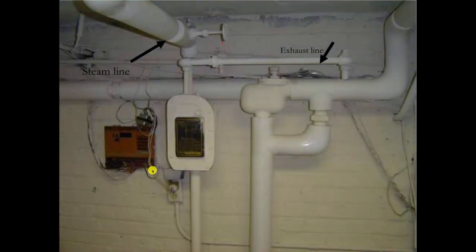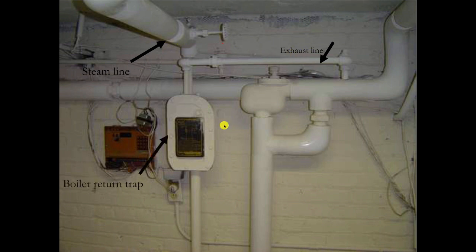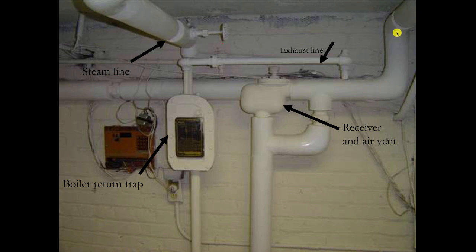This one was made by Hoffman. Over here we've got the return line coming back from the radiator. There's a steam line coming in here and an exhaust line coming over the top. This is the boiler return trap, and this is the receiver and air vent. This line goes out to the radiators — the steam line — and this line is coming back from the radiators. The condensate is coming out of radiators that have thermostatic steam traps on them. The condensate bypasses this line and goes back into the boiler. This exhaust line is equalizing the end of the dry return, coming back from the radiators, into the boiler return trap.